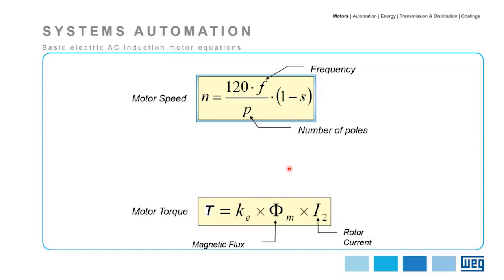Now, having the understanding that the VFD can change the frequency, let's take a look at some AC induction motor equations. The motor speed is defined by: 120 multiplied by frequency, divided by number of poles, multiplied by one minus slip. Keep in mind that the number of poles and slip are motor characteristics. Therefore, in order to change the motor speed, it's required to change the frequency — and this is exactly what the VFD does.